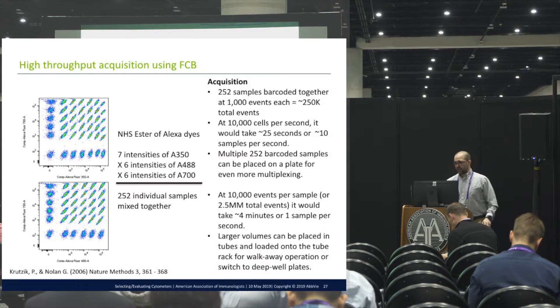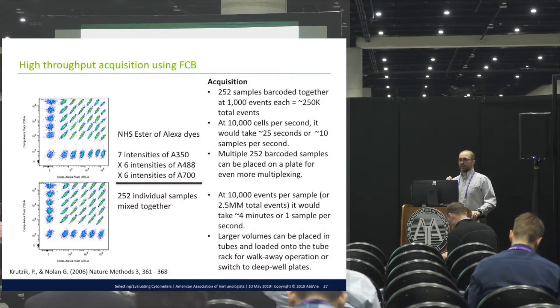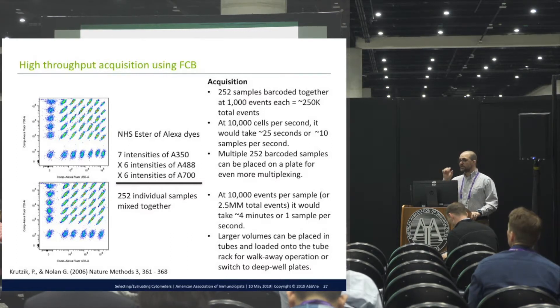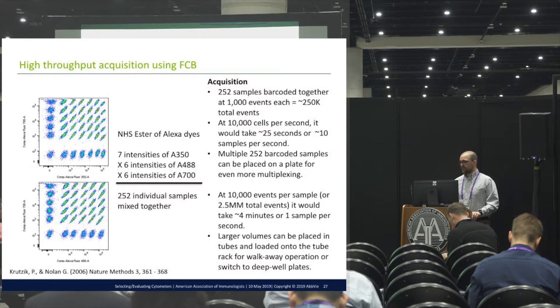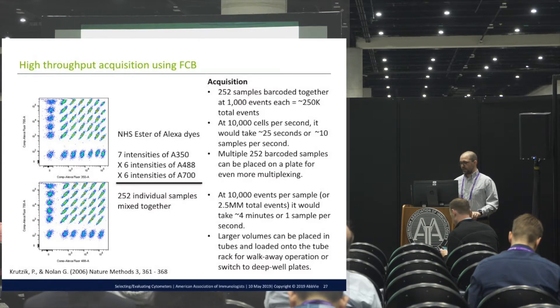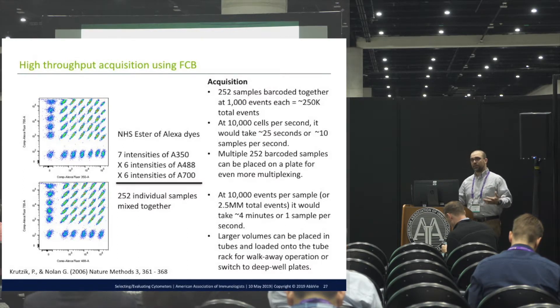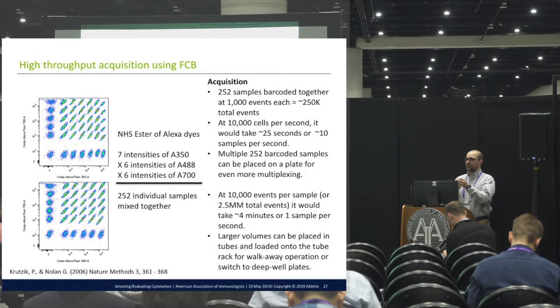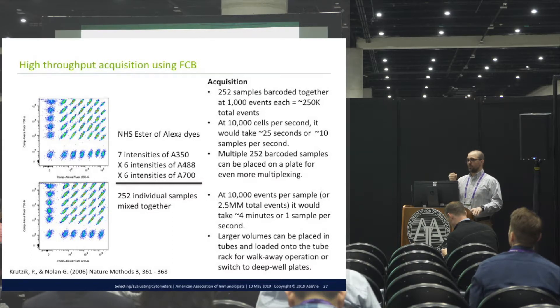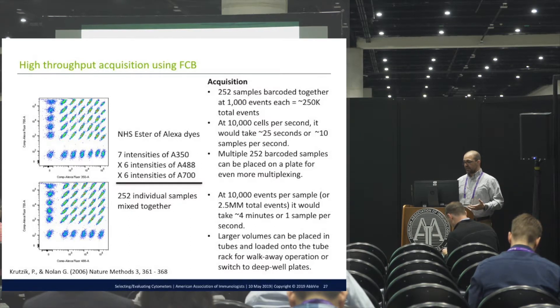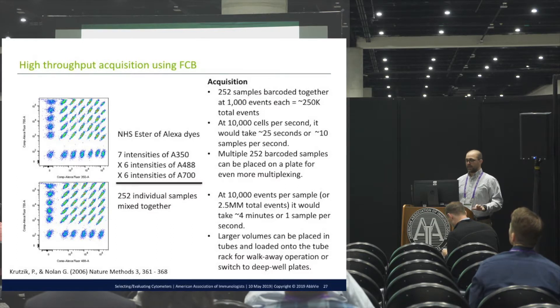Here's an example we ran in the lab. I'm using Alexa 350 — excited very well off the 405 laser even though it's technically thought of as a UV-excitable dye — along with Alexa Fluor 488 and Alexa 700. I have seven intensities of 350, six intensities of 488, and six intensities of Alexa 700. Seven times six times six is 252 samples pooled together in a single tube. The resolution is great — I can pick out even dim populations from the negatives with no problem, and I have enough dynamic range to have very bright and very dim things simultaneously.